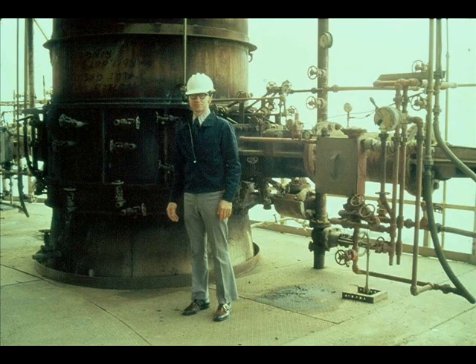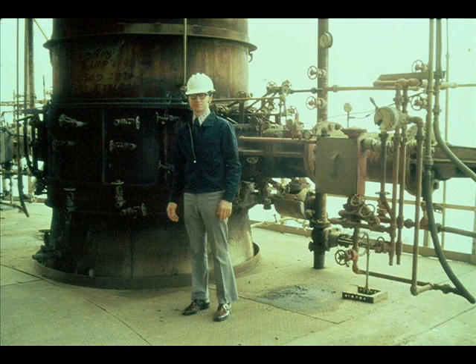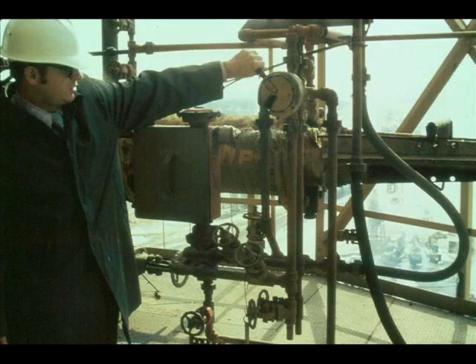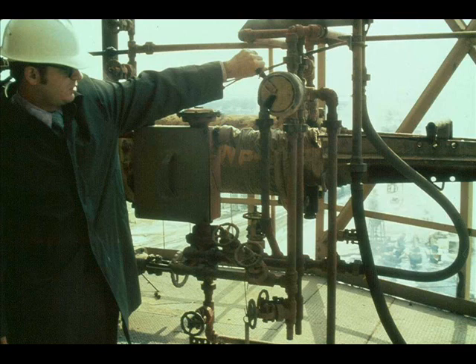Most valves that use hydraulic valve positioners don't have blocks and a bypass due to their large size. Therefore, if the positioner malfunctions, it has to be bypassed. To do so, obtain the operator's permission to bypass the positioner.